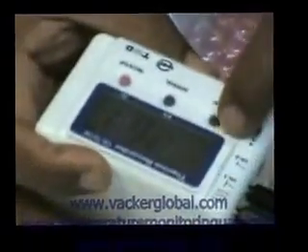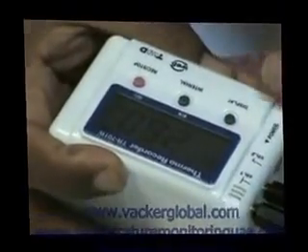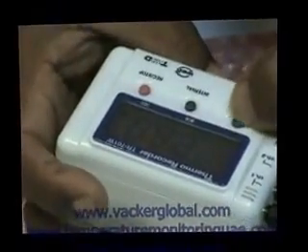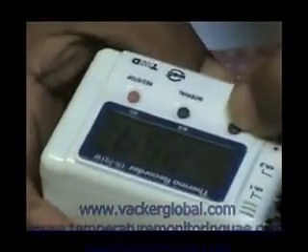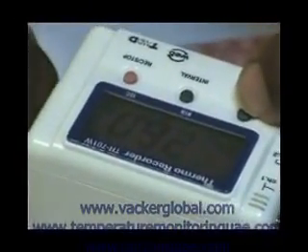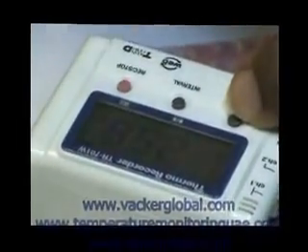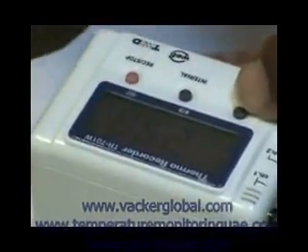That's all — now both the sensors are reading. You can see the temperature is reading: number one and number two, alternating like that. You can change the display by pressing this button: now it is only channel number one, now it is only channel number two, and now again both of them are continuously and alternatively showing.